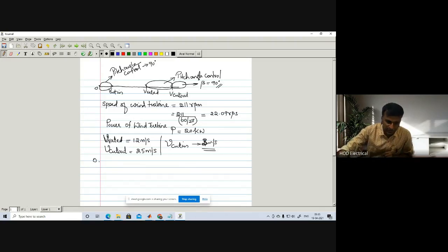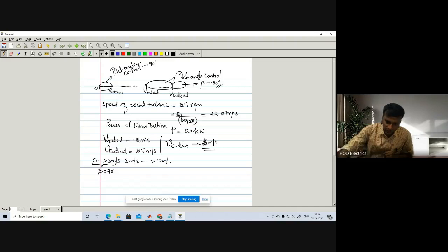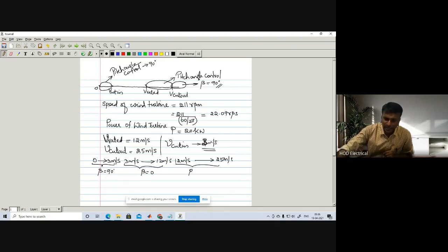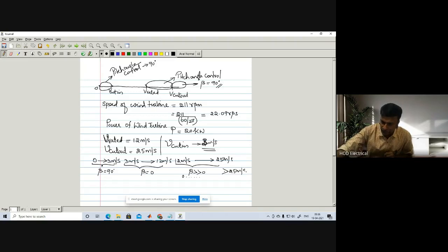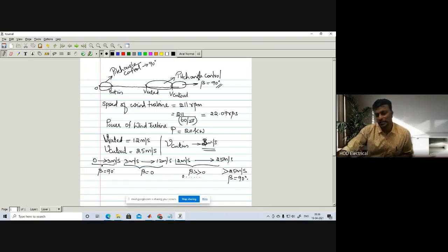So our region is: from 0 to 3 meters per second, we make pitch angle beta equal to 90 degrees. From 3 meters per second to 12 meters per second, we make pitch angle equal to 0 degrees. Then from 12 meters per second to 25 meters per second, we are increasing the pitch angle — going from 0 up to 10, 20, 30, 40 degrees. Above 25 meters per second, we again make pitch angle equal to 90 degrees. This is what we have planned.